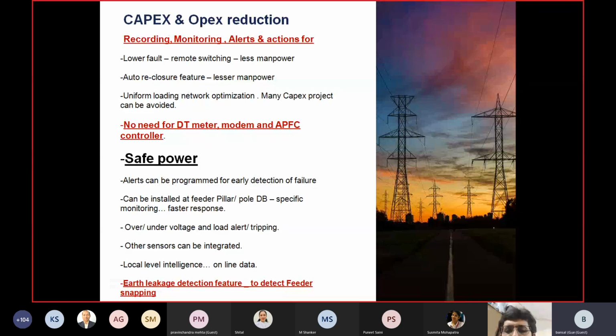Let me tell you the two big advantages of having more feeders. A, there is no fixed technical losses — if the current is zero, the loss will be zero, unlike in a transformer. And B, the more feeders you have, the current gets divided and the losses reduce. It also gives you flexibility to restore power from an alternate mode, and other benefits.